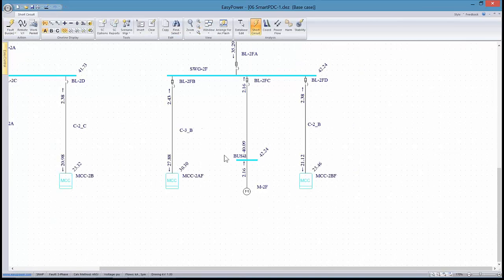So the significance here is, although the total current on this bus, if a fault were here, is 42,000 amps, you can see the net on this bus faulting is only 40,000 amps, with 2016 coming back from the motor. So the effect is to actually reduce the amount of current during a fault that this breaker will see.